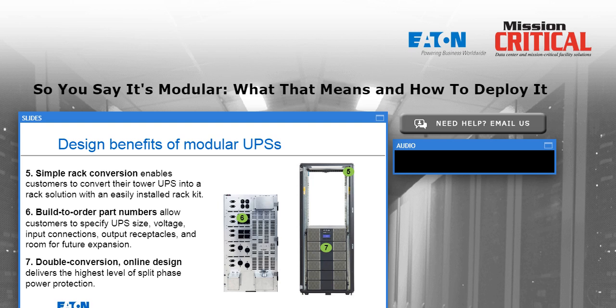so that they can support both higher voltage loads like 208 or 240 and 120 volt loads as well from that single UPS, and they'll choose 240 or 208 volt receptacles as well as 120 volt or IEC type receptacles. Lots of choices in a system like this because the customer will know that their needs may change over the life of this UPS.